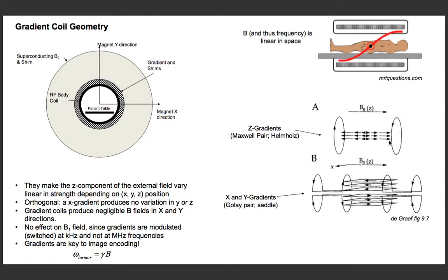So these are two simple loop coils. I'm showing them conceptually as simple loops. They're usually comprised in practice of more than the simple loops to improve their performance. But you can think of them as a simple loop coil here. And they're aligned, offset in this direction relative to the B0. So in this drawing of the scanner, there's one closer to you and one further away, and they're symmetric about the center of the scanner.